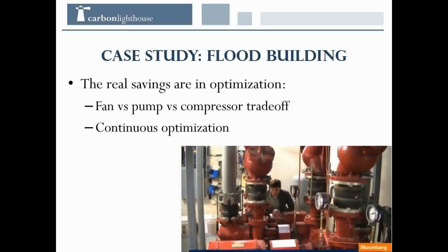In the building, there are cooling towers and water source heat pumps. If you use the fans more at the cooling towers, you give colder water to the heat pumps, so you get a fan penalty, but the heat pumps themselves become more efficient. Using data loggers to measure power, current, water temperature, fan cycle rate and other things, you can figure out exactly where the optimal point is.